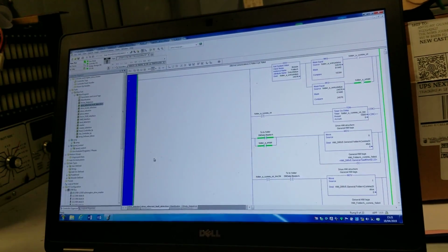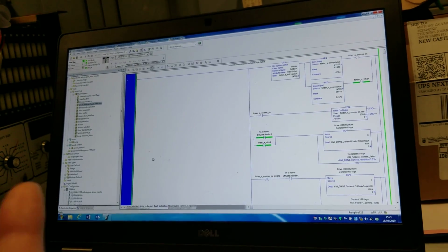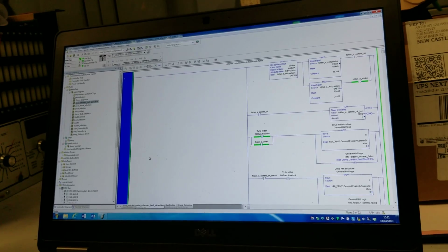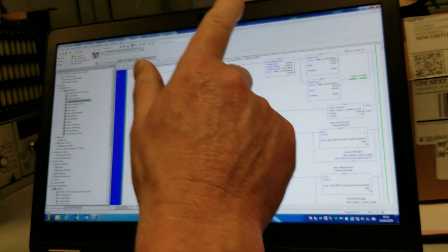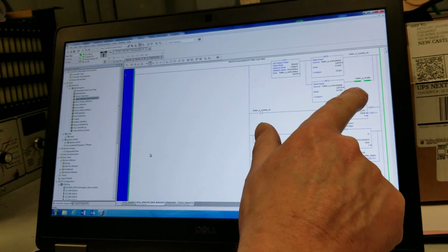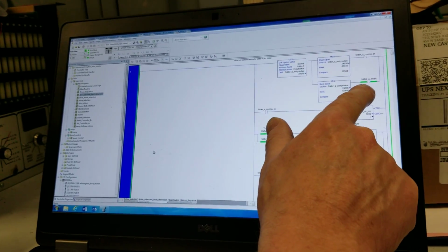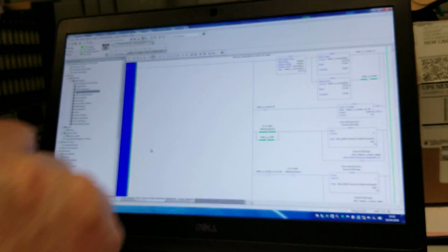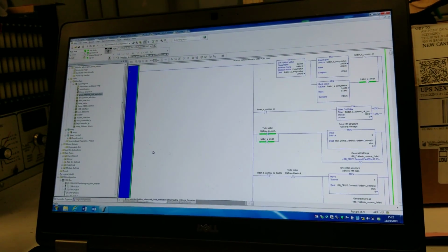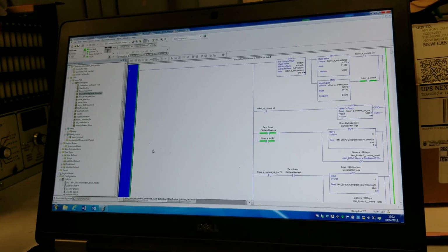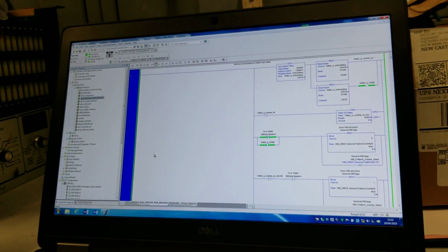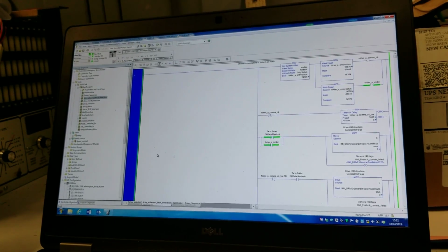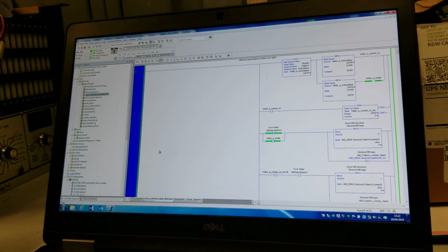Subsequently we light the lamp and put the status on the HMI. So if we've got one that says it's a comms fault, we would first look at this rung and determine whether it is inhibited when it's not supposed to be, or whether it's okay. Now I suspect if we got a red thing on there, we'll find that it's inhibited. So you go back to the previous rung, which was the selection, to check that the drive is selected. Although it could be active, it may not have been selected. Okay.